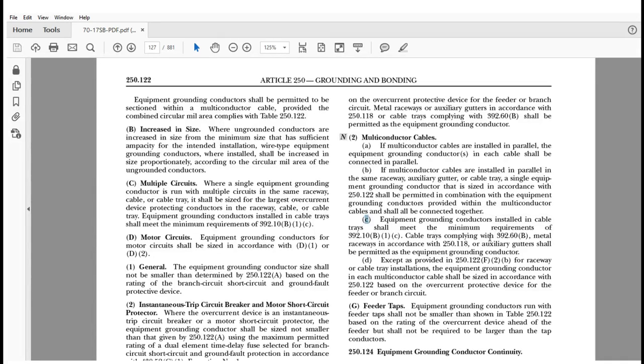Cable trays complying with 392.60(B), metal raceways in accordance with 250.118, or auxiliary gutters shall be permitted as the equipment grounding conductor. Again, they're saying, look, if you meet the requirements for that cable tray, in order to be considered an equipment grounding conductor, it's listed for that application. It meets the requirements as such for metal raceways under 250.118, like an EMT, rigid metal, those types of applications, then it is okay. It is adequate. You don't need to run the separate one. Okay? So we have some provisions here to do that.